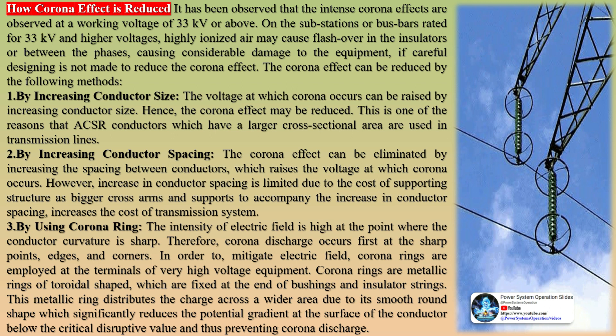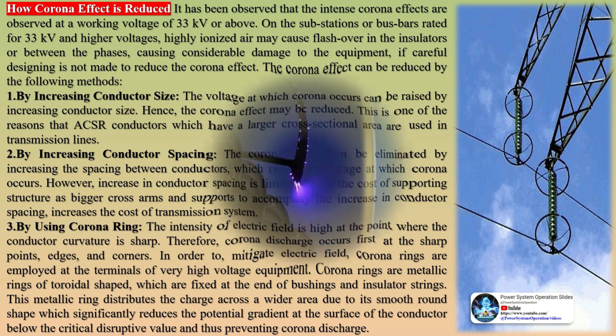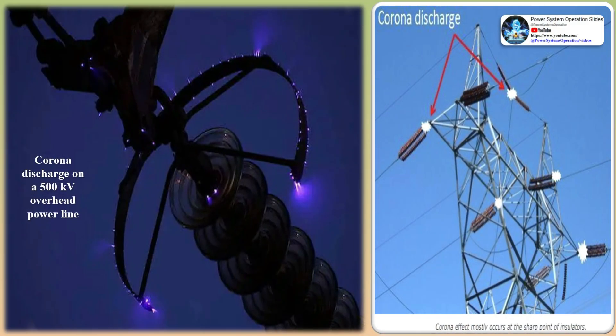Improving insulator performance by using insulators with higher pollution flashover performance and better contamination resistance helps mitigate the effects of corona discharge on insulator surfaces, reducing surface leakage current and corona losses. Optimized transmission line routing — planning the route of transmission lines to avoid areas with high pollution levels or adverse environmental conditions — minimizes surface contamination on insulators, thereby reducing the risk of corona discharge. Using conductors with larger diameters reduces the electric field intensity around the conductors, and increasing conductor size also reduces the surface current density, which can contribute to corona formation.